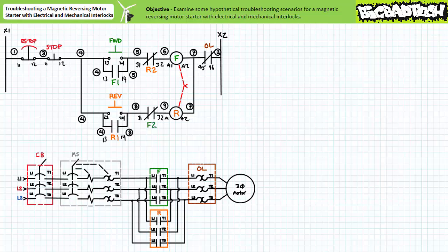Note that this magnetic reversing motor starter with electrical and mechanical interlocks exhibits low or no voltage protection characteristics, and that if power is lost and restored, the system will not immediately restart until an operator makes a conscious decision to do so.